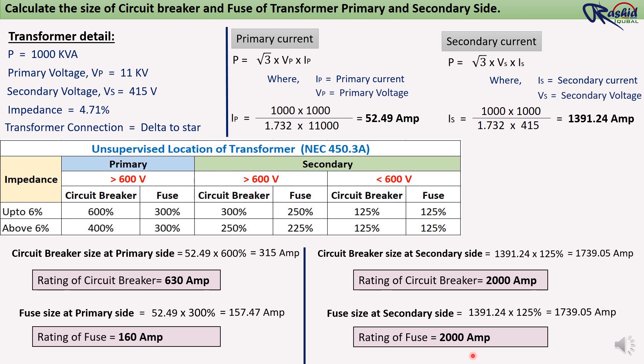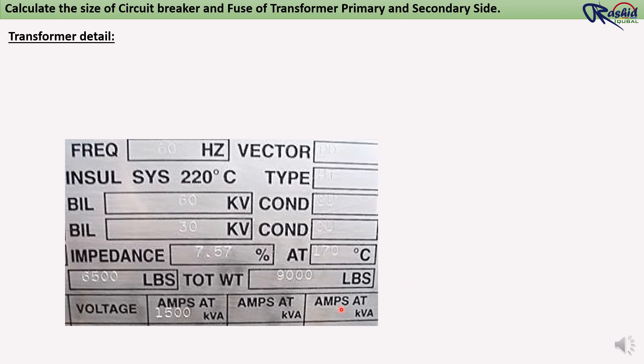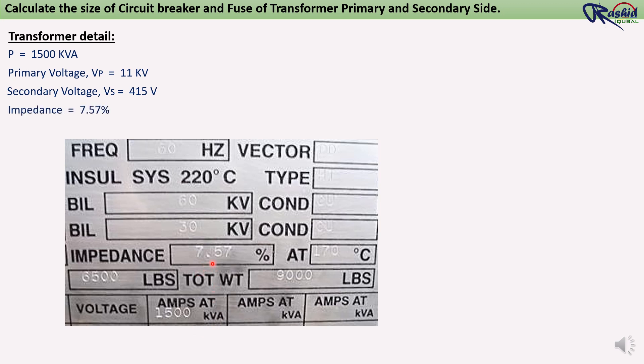Let's see another example: if impedance is more than 6%, how do we do the calculation? From the nameplate, transformer rating is 1500 kVA, primary voltage is 11,000 volts, secondary voltage is 415 volts, and impedance is 7.57%. So first we need to find out the primary and secondary currents.